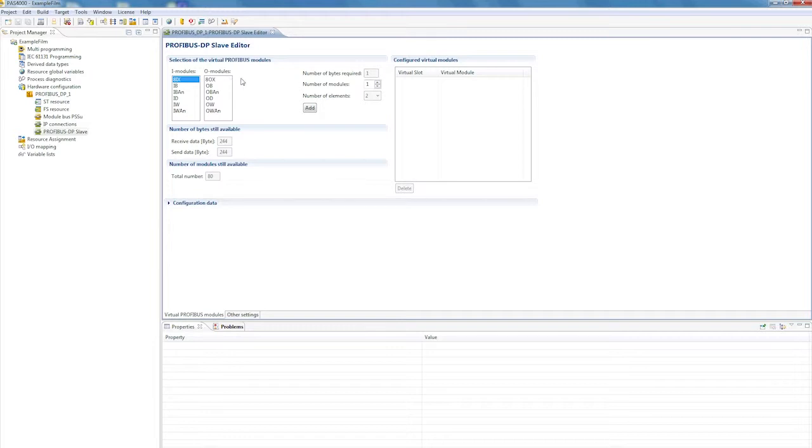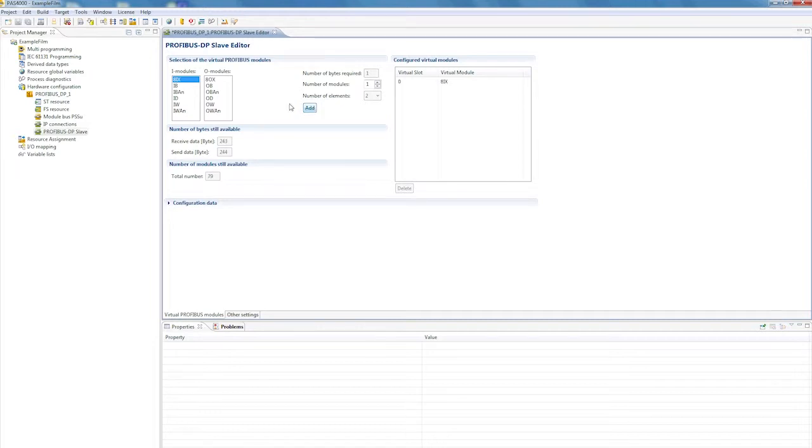Let's start with a specific example. First, we'll configure the received data modules, which are to be sent from the external Profibus master to the PSS 4000 device. For example, an 8-bit array is followed by two word data types, and then another word array with two elements.